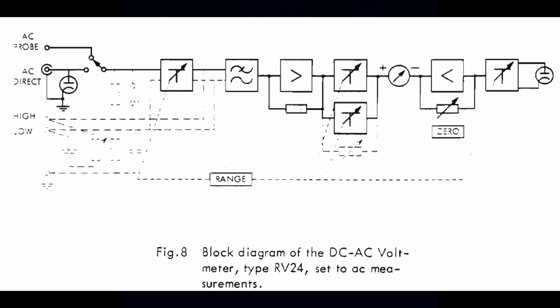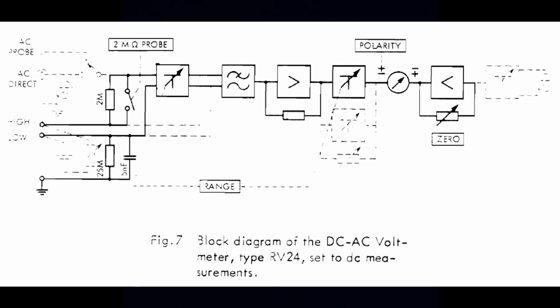Here's the block diagram in AC mode. We've got two different AC inputs. You can use an external AC probe. That means the rectifier is external, and then there is a filament voltage in this connector to the external AC probe. And this will of course give you an extended frequency range, or you can go directly into the built-in rectifier tube system. It's called AC direct, as shown here. In DC voltage mode, we need to use the high and low banana jacks, and it shows the input impedance here. There is 25 megohms to chassis, so you can have 400 volts floating to chassis and to mains ground.